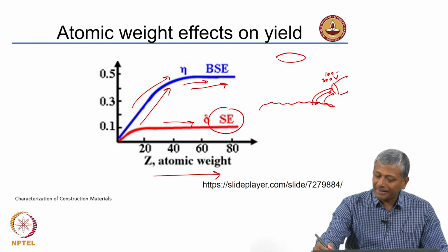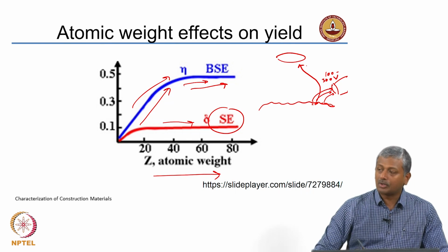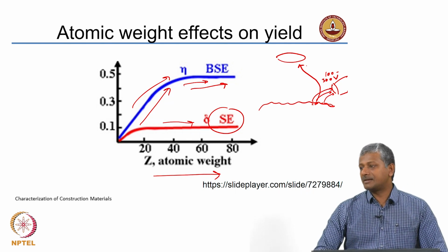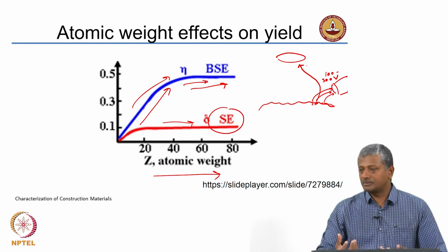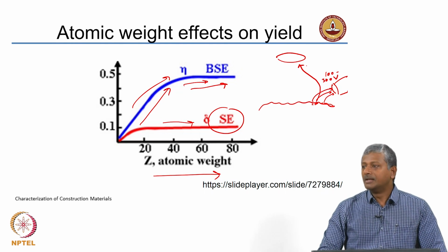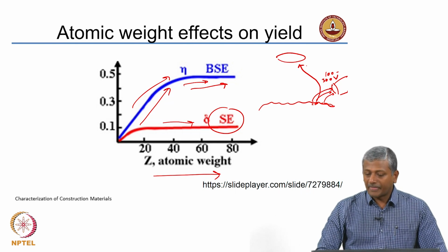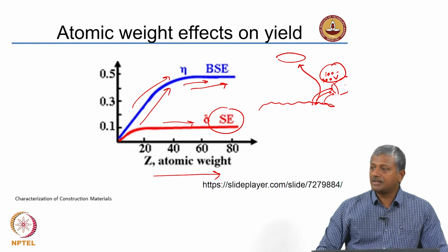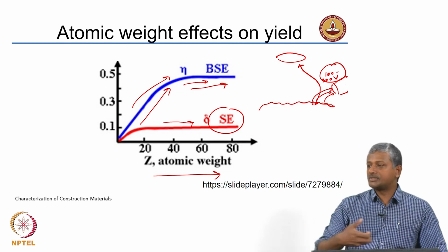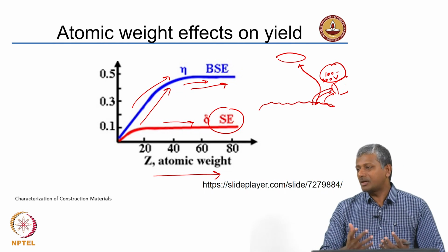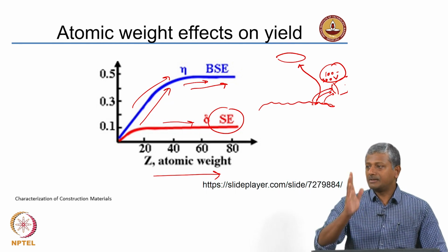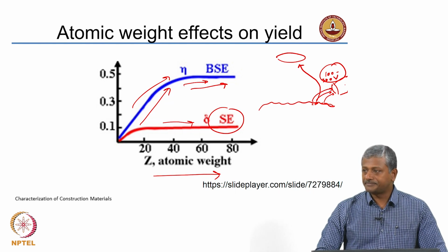So, it is very rare that some secondary electrons will deflect all the way and go to the backscatter detector. It may happen because a lot of electrons are getting generated on the surface. Some electrons may have sufficient energy to actually go right up, but the charge here with the Faraday cage will be able to pull many of these low energy electrons towards the cage, and you may not have any specific instances of these electrons going to the backscatter.